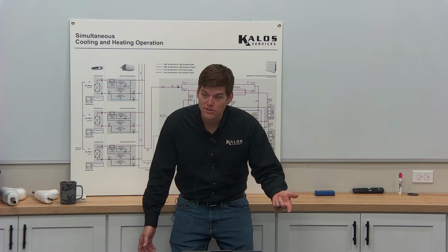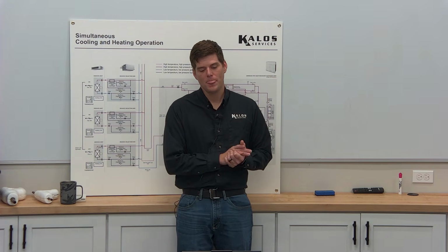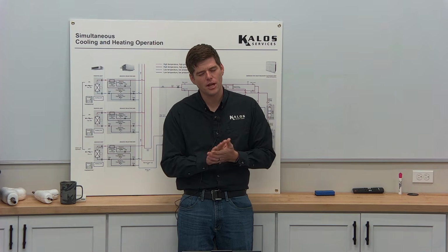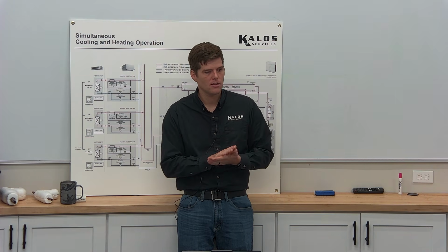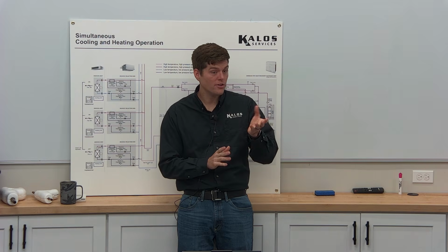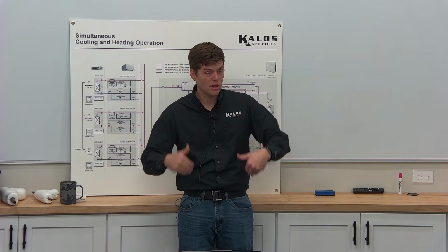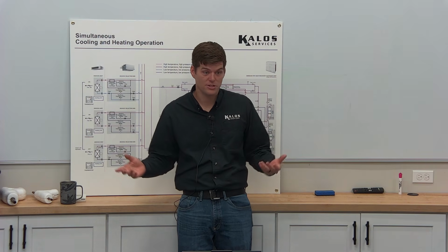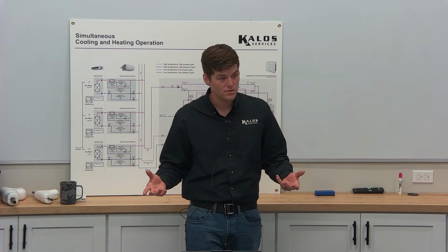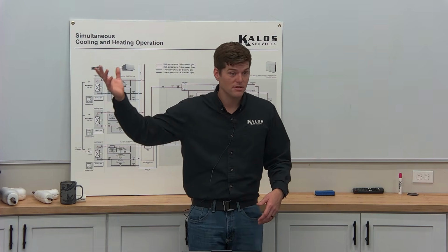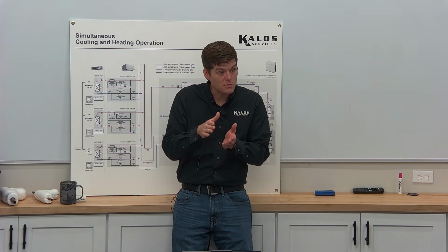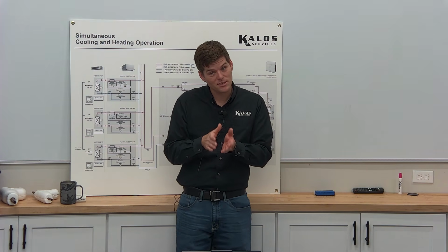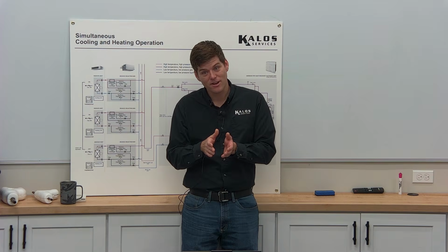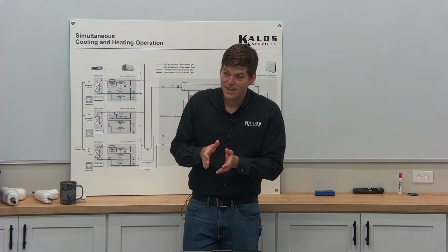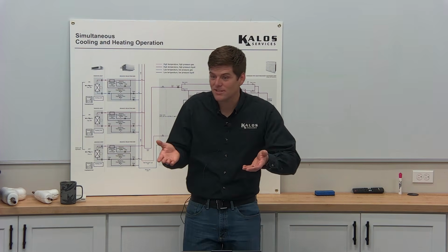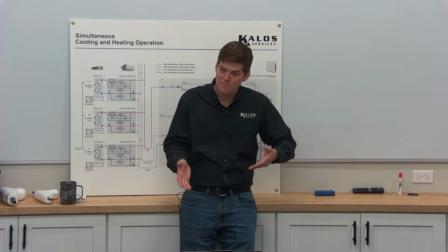You take liquid refrigerant. So let's think about this concept, right? Does anybody know what the average temperature of an engine in your vehicle should run at? Around 180, 200 degrees, depending on the model, right? Anything below that, compression's not great, right? You get a lot of problems, you get a lot of issues. Above that, it's too hot, right? Can't function. There is a sweet spot with inverter boards. We don't need to keep these in sub-zero temperatures of 0 degrees, right? The liquid temperature is not that cold, so it's not going to. And it's a liquid. It's not going to change states. Right. You can add heat back to liquid.